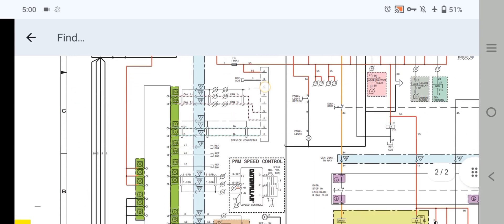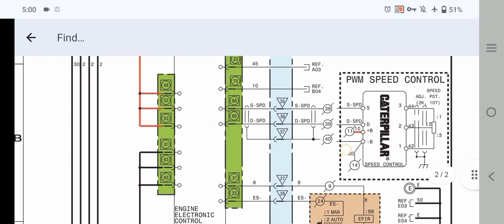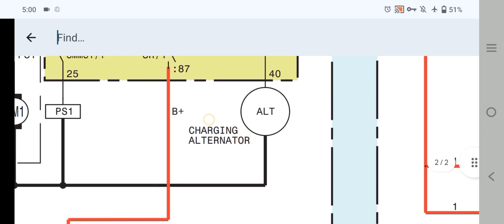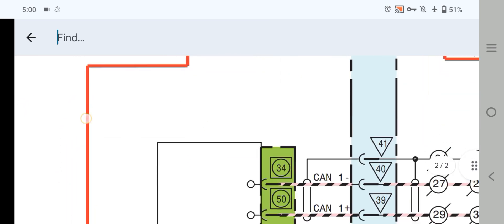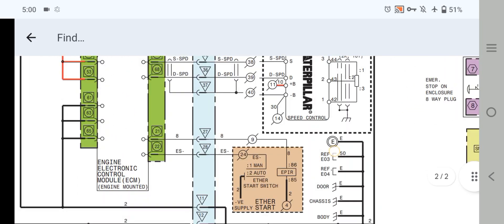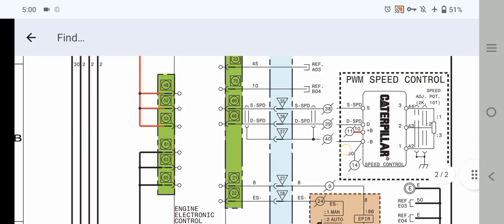For the Caterpillar EMCP 4.1 and 4.2 — if you have a problem where your generator is not cranking and not starting — first of all, check the ECM power and grounds. Also check the emergency push button wiring connections and wiring diagrams, verify the fuel start and stop relay, and check your fuel stop and start solenoid. We will start from the ECM power and grounds.